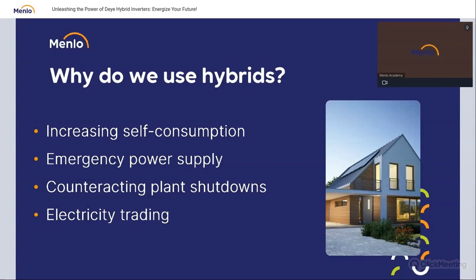Third reason why do we use battery system, hybrid system, which cause that government push us to do that, is counteracting plant shutdowns. It's connected with increasing self-consumption, because if you don't send energy to the grid, it is not overloaded. If it's not overloaded, the voltage doesn't go so high to turn off your PV installation. Thanks to batteries, you can release some limits from the grids and allow all PV installations to work perfectly fine.